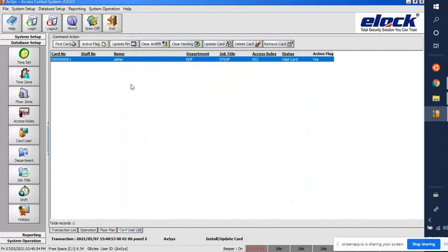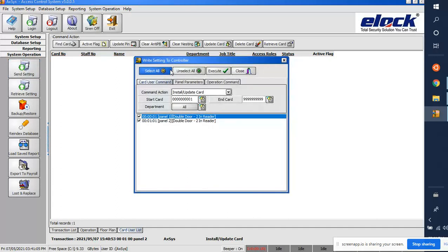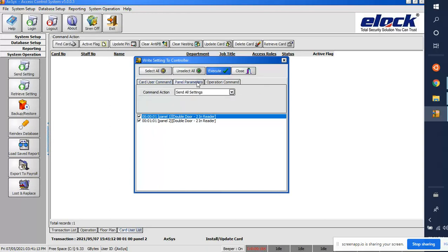For this user, access role 002 is now assigned. We need to send these settings to the board. Go to System Operation > Send Settings, then select 'Card User Command', click on panels, and execute. Also run 'Panel Parameters' and execute.